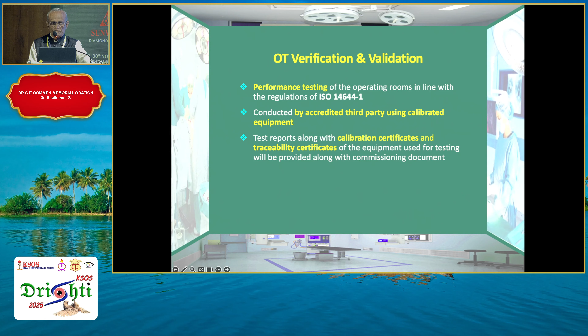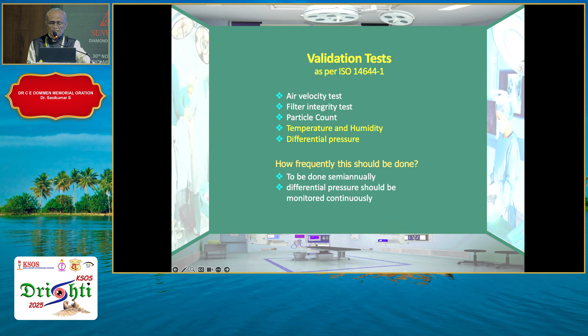These parameters, air velocity test, filter integrity test, particle count, temperature and humidity, and differential pressure, have to be checked periodically, of which the other parameters need to be checked only once in 6 months, but the temperature, humidity, and differential pressure have to be monitored continuously, which will be displayed in the panel.